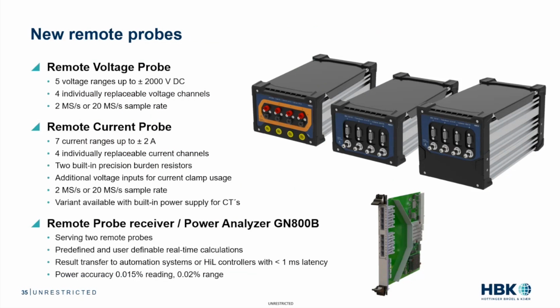What we have is a voltage probe, or as we call it, a remote voltage probe. You've got 5 voltage ranges you can choose from, up to plus/minus 2,000 volts DC. So this is going to be able to handle not only the present trend of voltages, but also future higher voltages that are forthcoming. You also have 4 individually replaceable voltage channels on the voltage probe, and it samples at 2 million samples per second, which is very well sampled.